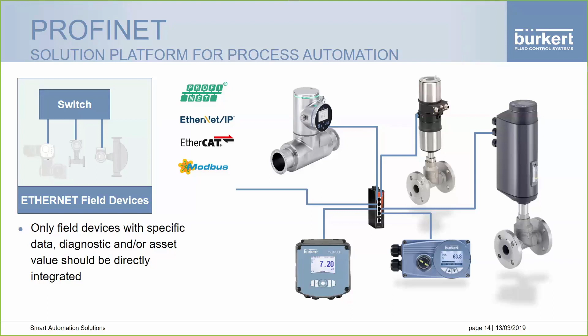There are still limitations. Ethernet is a great network, as we know from computers, but it doesn't carry power, so we need separate power runs. We're also limited to 100 meters, and it's really a star topology. Even though most Ethernet devices have two ports and can look like a daisy chain, each device is essentially running a small switch, so it's technically a star topology. This is how Ethernet mounts directly in the field.